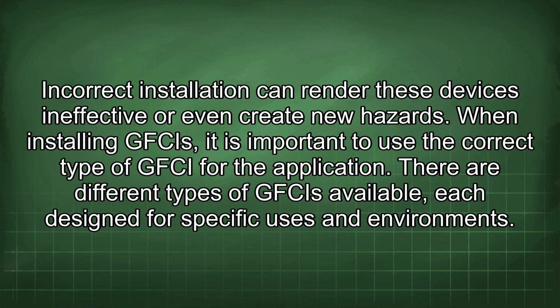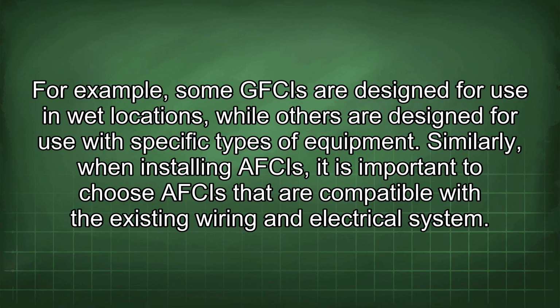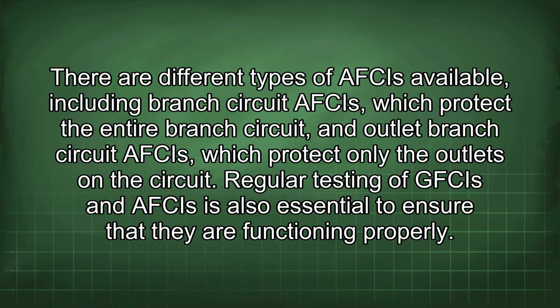When installing GFCIs, it is important to use the correct type of GFCI for the application. There are different types of GFCIs available, each designed for specific uses and environments. For example, some GFCIs are designed for use in wet locations, while others are designed for use with specific types of equipment. Similarly, when installing AFCIs, it is important to choose AFCIs that are compatible with the existing wiring and electrical system. There are different types of AFCIs available, including branch circuit AFCIs, which protect the entire branch circuit, and outlet branch circuit AFCIs, which protect only the outlets on the circuit.